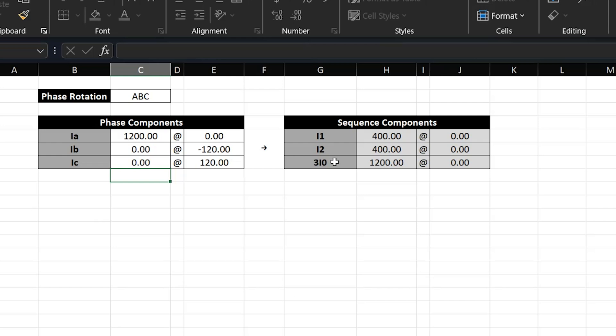The reason I'm using 3I0 is because relays typically use 3I0 instead of I0 for the set points of protection elements. For example, in SEL relays the ground overcurrent protection elements operate off of the 3I0 current, not I0. So I've set up this calculation to use 3I0 just to make it more convenient for setting protection elements.